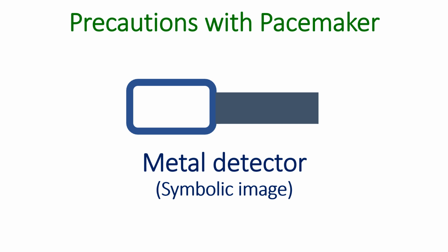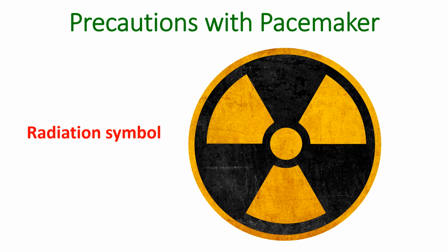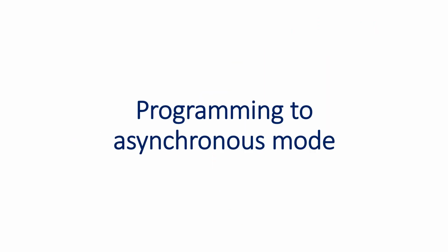Other important electromagnetic devices are metal detectors at airports and theft detectors at malls. An identity card will be needed at airports to avoid metal detectors. In the hospital, there are several devices which can generate electromagnetic waves, like surgical cautery, defibrillators, radiation therapy, dental instruments, nerve and muscle stimulators, which need special precautions. Using bipolar cautery and using cautery in intermittent short pulses can reduce the interference. Pacemaker can be programmed to operate continuously prior to the procedure. Reprogramming is done after the surgery.